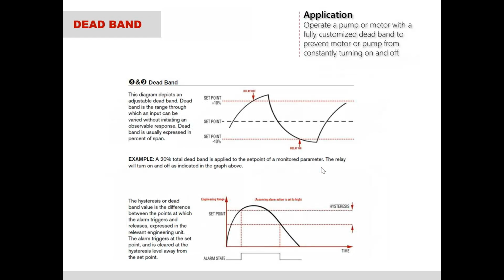The most common way that this switch is used for our 800 series or our 815 is the deadband option. So if you're familiar with our mechanical pressure switches, the biggest drawback of a mechanical pressure switch is that you can't really define what the deadband is. For most models, the deadband that you receive is what it is. You can't adjust it. There are mechanical pressure switches that have adjustable deadband, but they are limited in what you can do. And also they can be a little wonky as well.